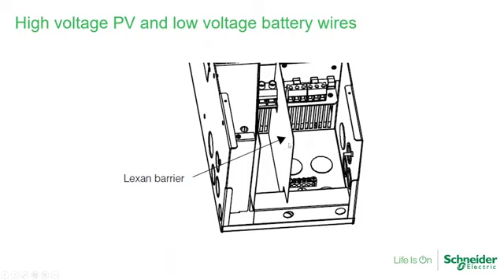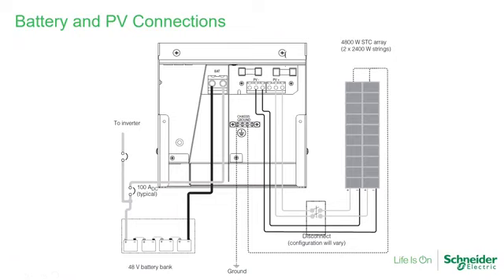One more thing here, and I think the next view will show it a little bit better: this piece here is an aluminum tray intended for the communication cables. So you want to make sure that you're not running communication cables here with the current carrying conductors. The tray, not really clear in my picture here, continues. So if you have multiple charge controllers, you can run the communication cables through this smaller knockout. Ideally, especially with big systems like the one I showed in the previous photo, there will be so much noise on the conductors that are carrying current that it will absolutely interfere with the communication. So it's absolutely mandatory that you run communication cables through this pre-designed aluminum tray, which is also grounded, by the way.